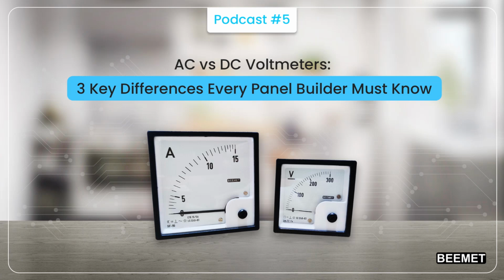Now let's look at some common mistakes made while selecting voltmeters for panels. One common mistake is using a single meter to measure both AC and DC, which often leads to incorrect readings. Another issue is ignoring waveform distortion, which can result in inaccurate readings, especially in AC systems. Neglecting proper isolation can also create grounding problems within the system. Additionally, not properly evaluating the meter before selection can lead to instability during operation. Finally, let's wrap up the key takeaway.